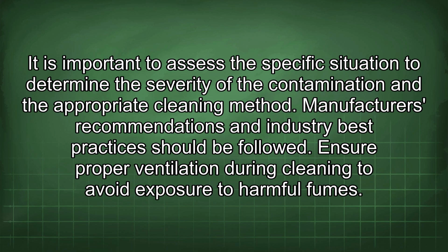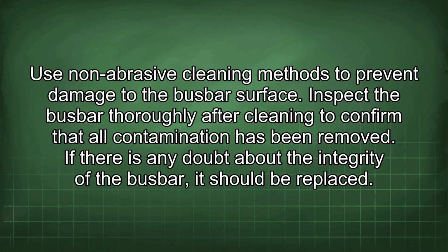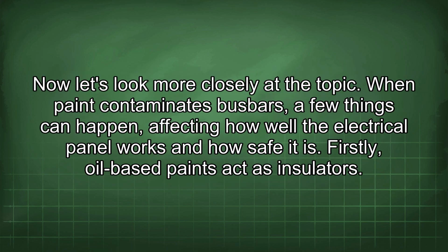Ensure proper ventilation during cleaning to avoid exposure to harmful fumes. Use non-abrasive cleaning methods to prevent damage to the busbar surface. Inspect the busbar thoroughly after cleaning to confirm that all contamination has been removed. If there is any doubt about the integrity of the busbar, it should be replaced. Now let's look more closely at the topic.